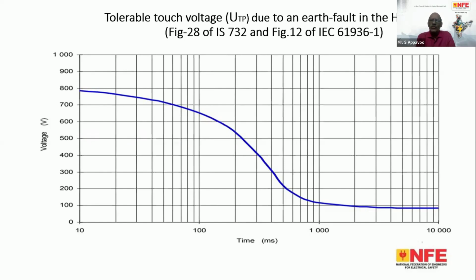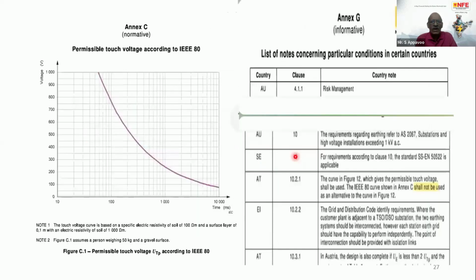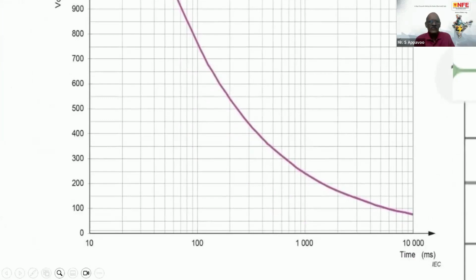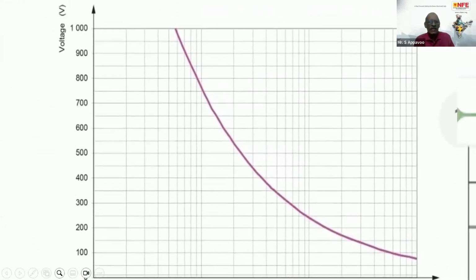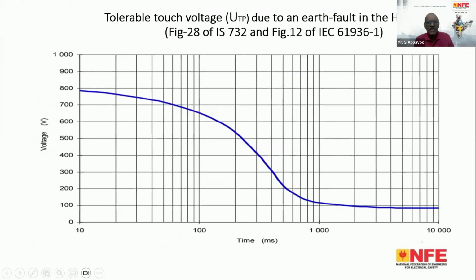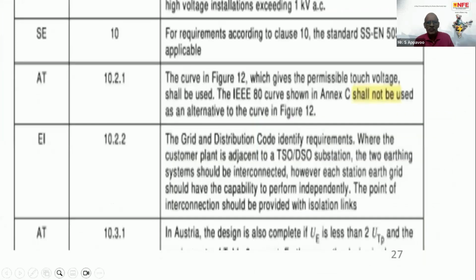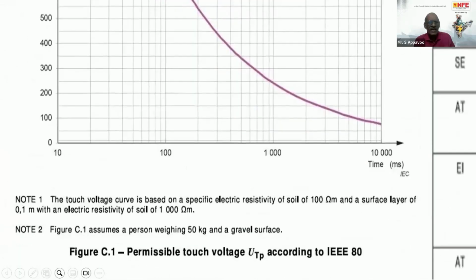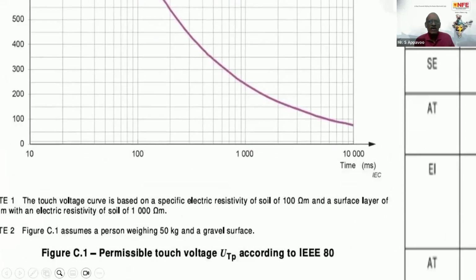So it may be required to go for more stringent earth resistance values as the fault level of the DISCOM increases. Such a low value of earth resistance can be achieved by adopting a global earthing system only, which is not possible in domestic premises. That's why, in the IEC country notes, it is clear that some countries adopt the IEC 61936. This is the IEEE curve. In the previous curve, the value varies at 200 milliseconds. So this is somewhat more stringent than this IEEE curve.